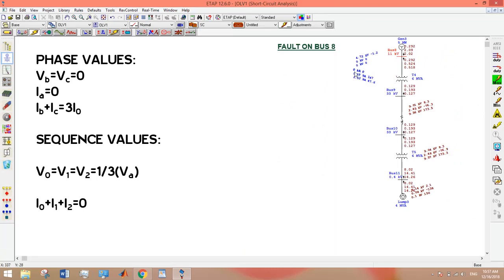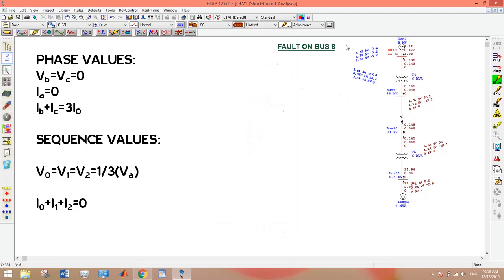We can verify our findings here on ETAP. It is clear that VB and VC are zero, and IA is zero. You can use a calculator to verify the expression IB + IC = 3I0. For sequence values, verify the expression I0 + I1 + I2 = 0 using a calculator. It is clear that the sequence voltage components are equal among themselves and also equal to one third of VA.